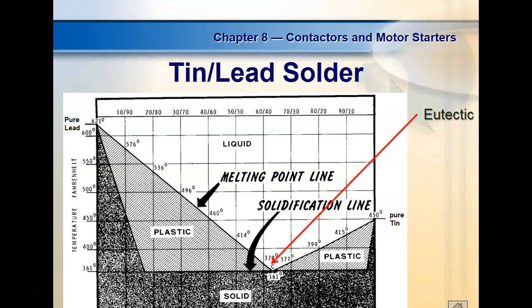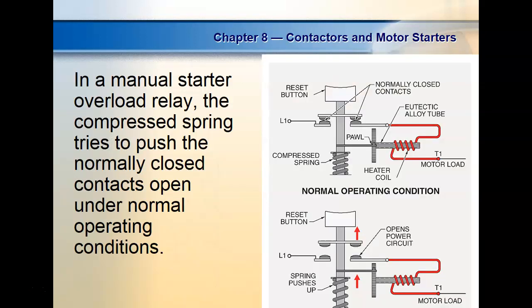And always, when you play with lead, you need to be careful. Anytime you handle lead, you need to make sure you wash your hands when you get through, right? Not hand sanitizer. Hand sanitizer just sanitizes the lead. It's still dangerous. So this is basically the way it works, guys. These heater overloads, we have to put the right size heater in there, right? Understand that. Depending on the amount of current, overloads are not rated in voltage. Overloads are rated in current.